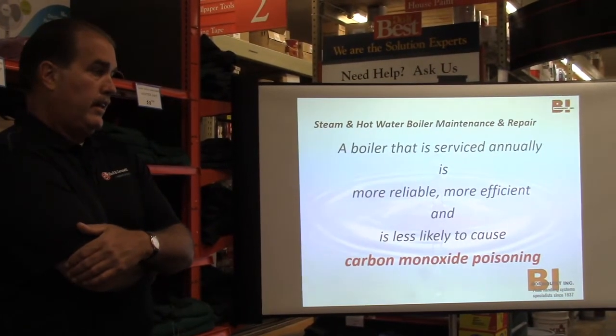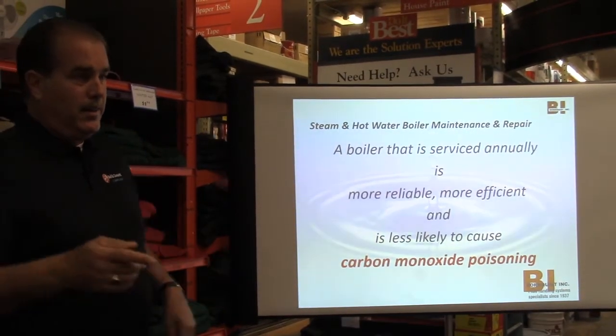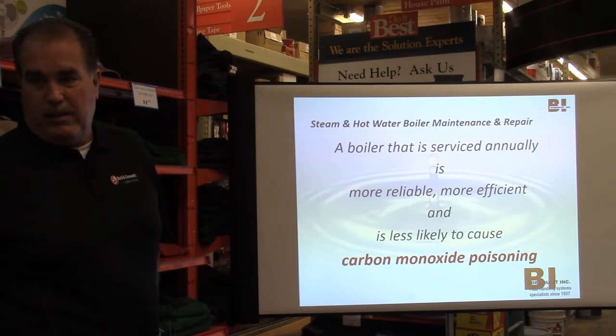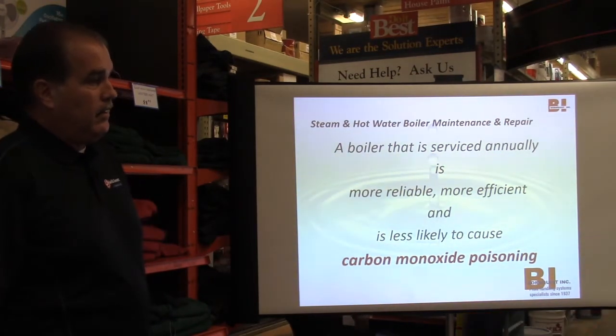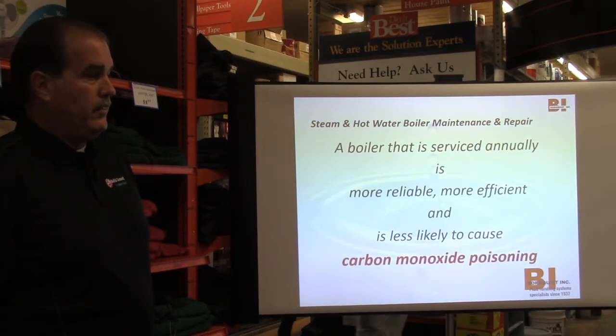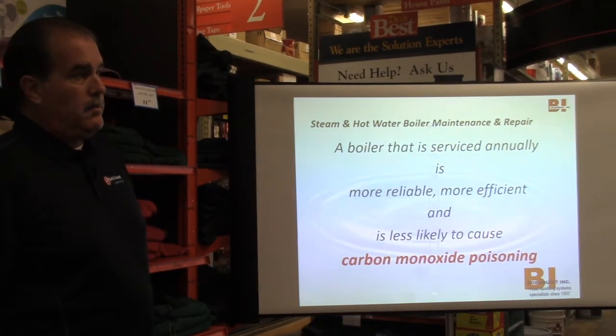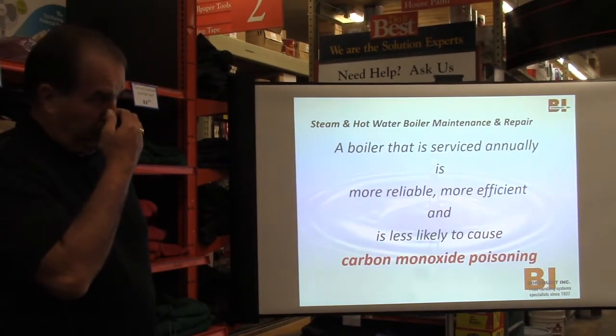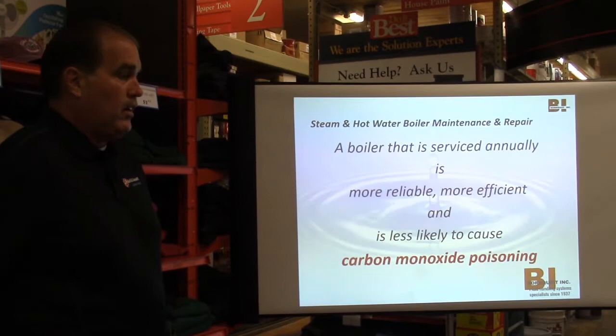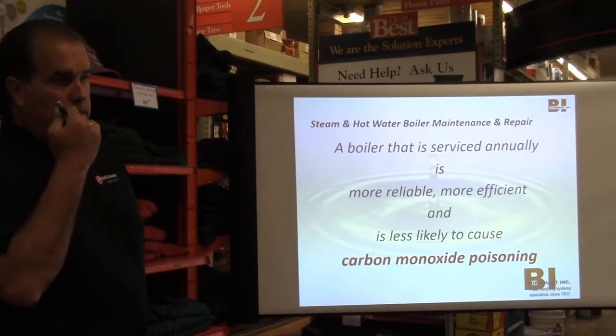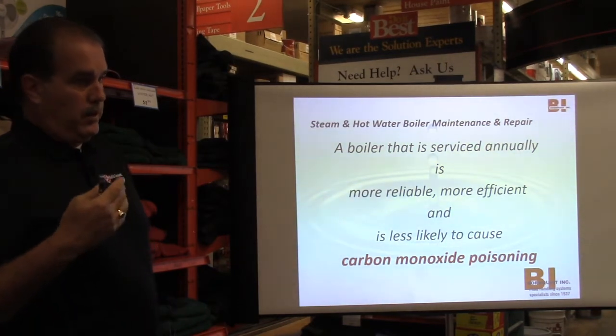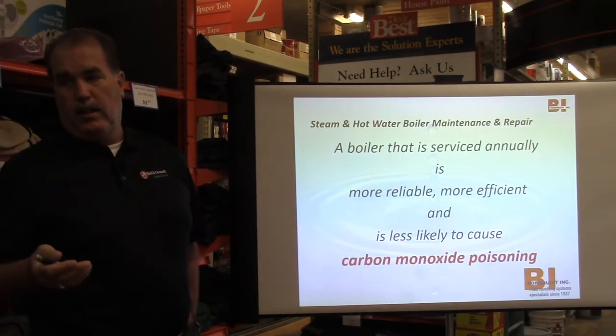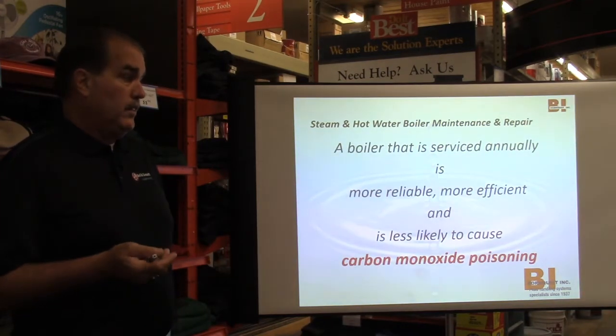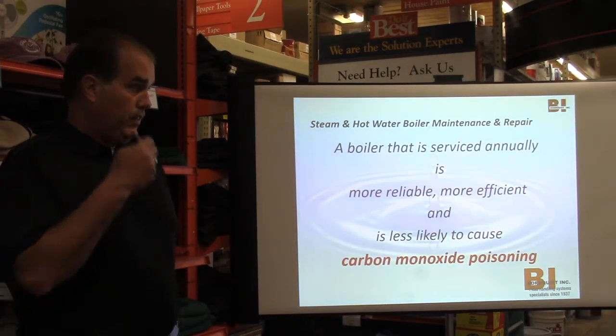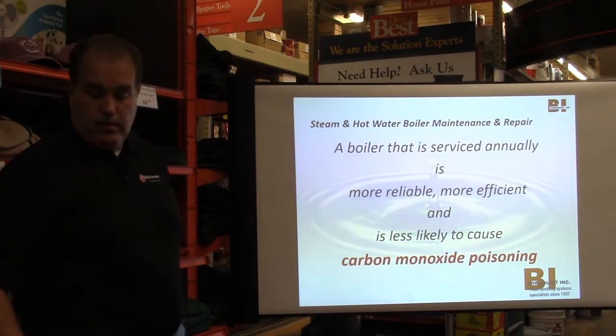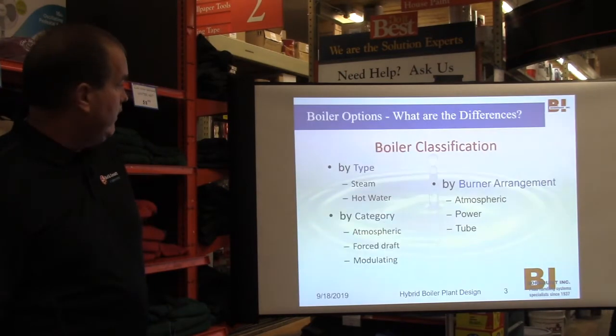Basically what they're going to do, not unlike a car, they used to, back in the day, stick that little tube up the exhaust to monitor the exhaust quality. Same thing with boilers. They have devices that they use to do that. And the idea behind that is because if you let the boiler get really dirty on the flame side, the biggest issue that we're all concerned about is carbon monoxide poisoning. Because if that boiler gets plugged up enough, you actually can create an unsafe condition that you can hurt yourselves, or hurt the occupants of the building or whatever. So be very, very cognizant of that.